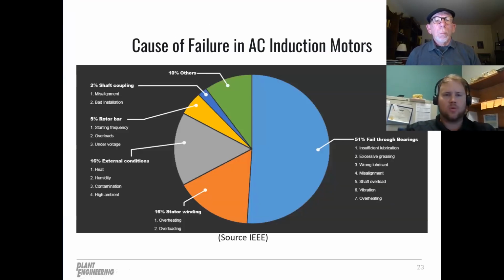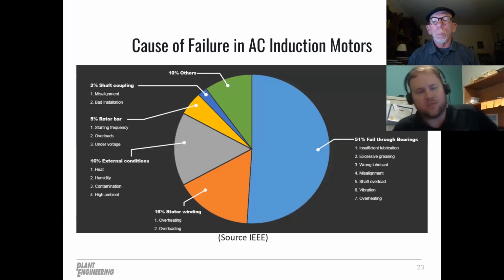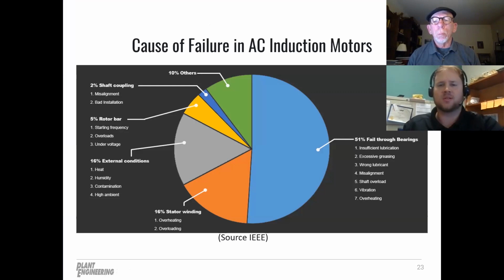So I did say we would come back to causes of failure. And so here you will see a graph that I took from the Institute of Electrical and Electronics Engineers website, IEEE. You see here bearing failures, very high on the list. Some issues they list: insufficient lubrication, even excessive lubrication, using the wrong lubricant, wrong grease. And then also vibration is mentioned, right? Parallel and angular misalignment. We talked about that a little bit earlier.